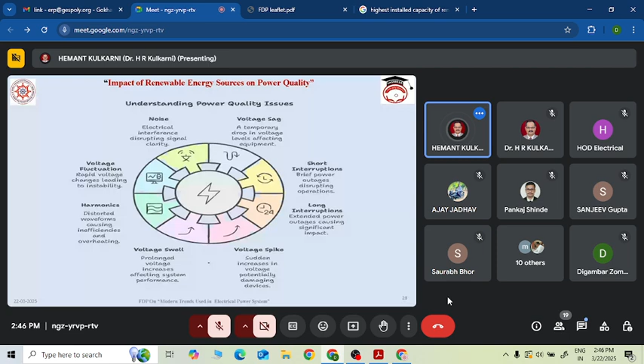Voltage sag - what is voltage sag? I am trying to explain it in short: this is the most common problem in which voltage drops from 10 to 90% of the normal power frequency voltage. So there is a drop in voltage from 10% to 90%, and this may last up to 1 minute.